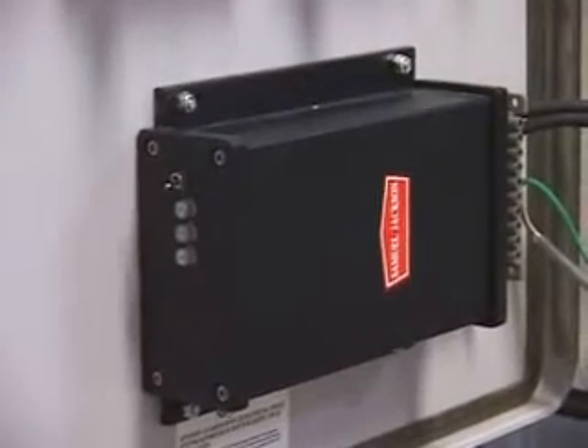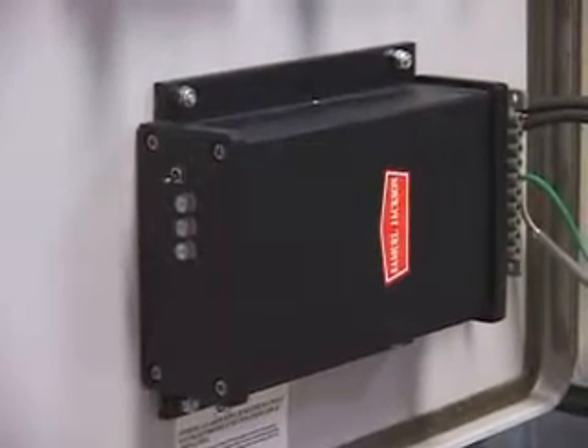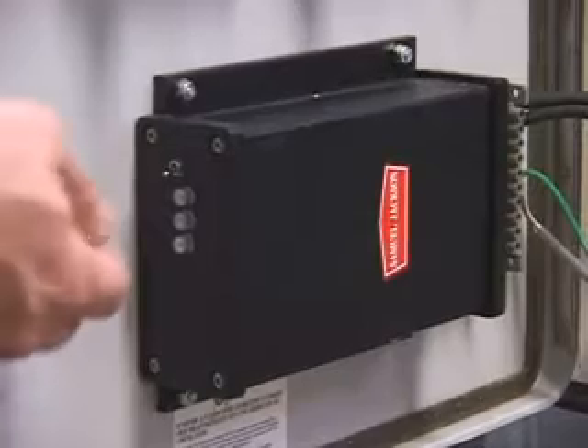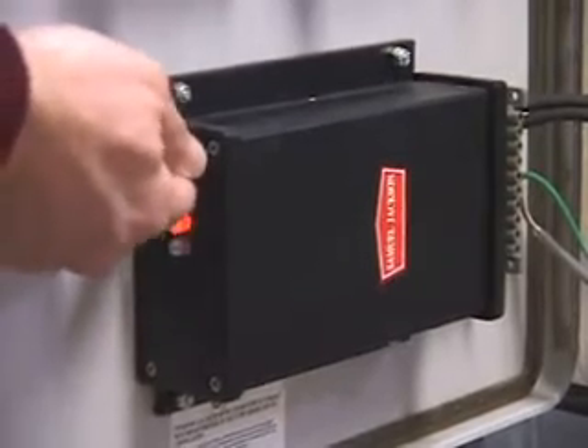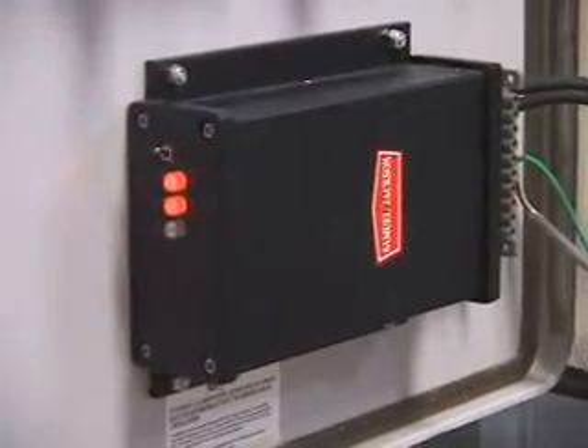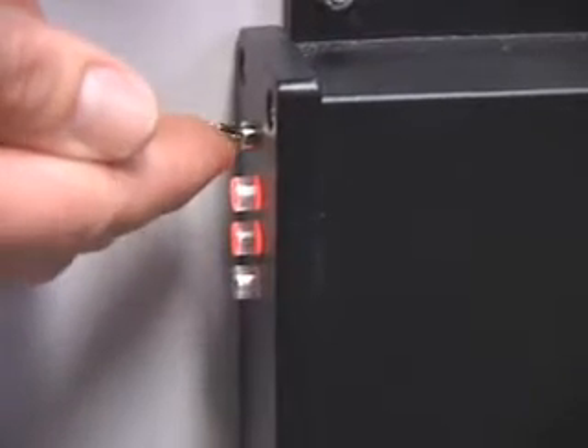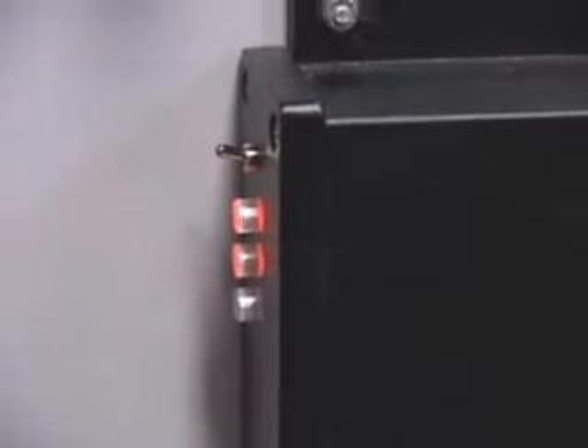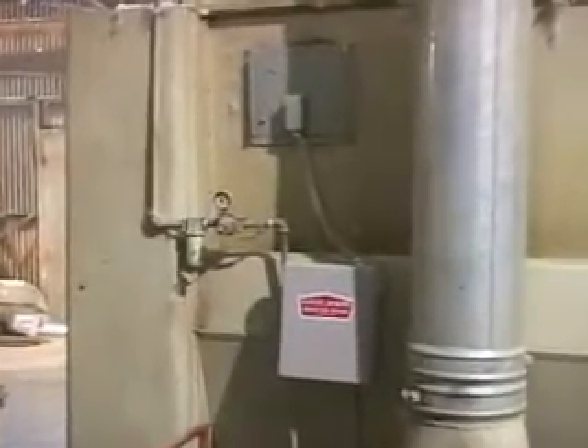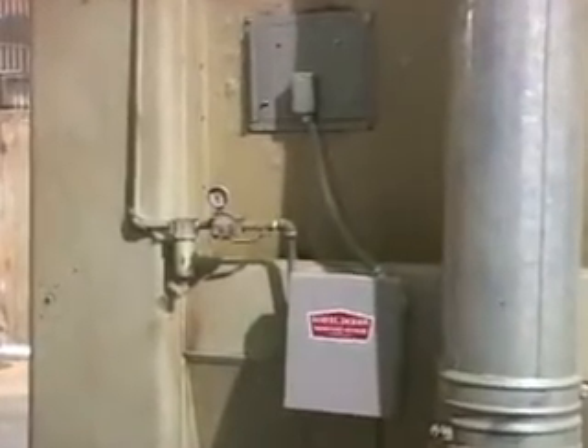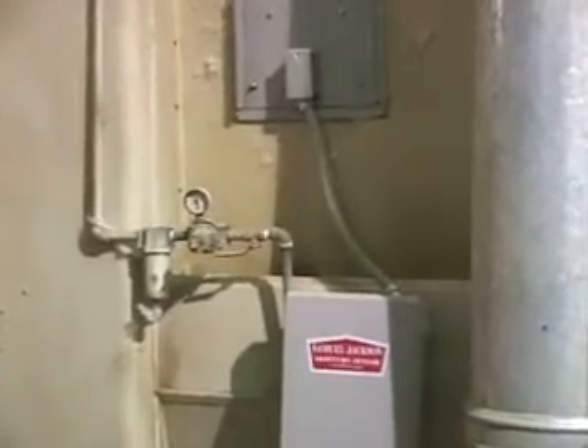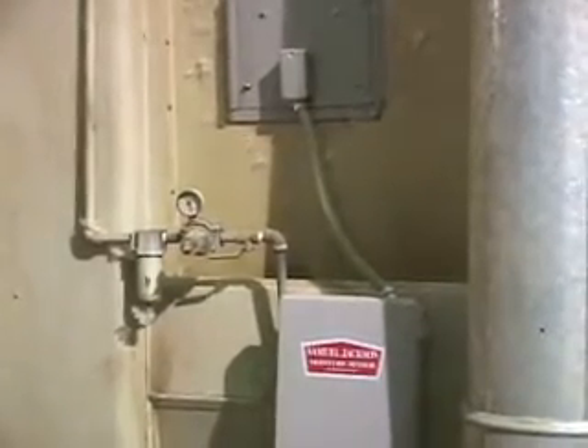When 24 volt DC is present on the transmitter, 2 red lights will illuminate, showing that the transmitter is working. Some transmitters have a small power switch. If you do not see the red lights, make sure this switch is turned on. Use this technique to make connections to all of the Samuel Jackson moisture sensors in the gin. The service manual contains details of which wire numbers correspond to each sensor.